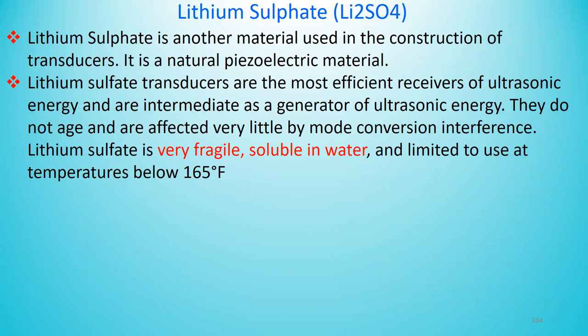Lithium sulfate is another material used in the construction of transducers. It is a natural piezoelectric material. Lithium sulfate transducers are the most efficient receivers of ultrasonic energy, and an intermediate generator of ultrasonic energy. They do not age and are affected little by mode conversion interference. Lithium sulfate is very fragile, soluble in water, and limited to use at temperatures below 165 degrees Fahrenheit.